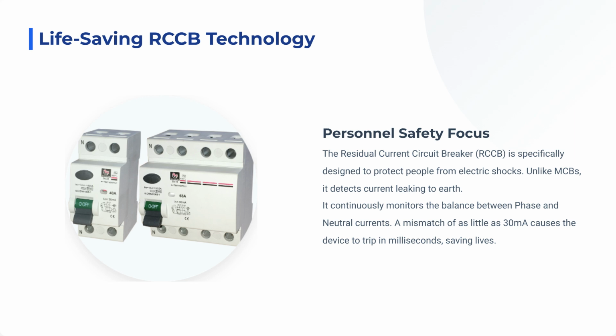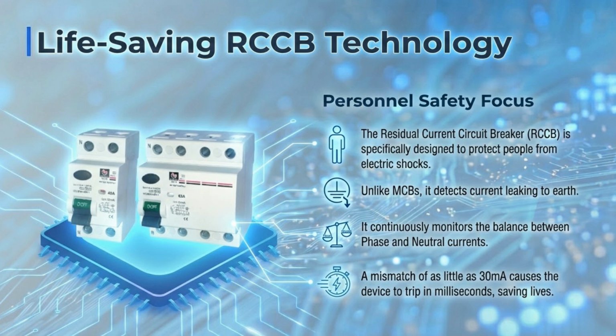The residual current circuit breaker, or RCCB, is focused on personnel safety. It detects current leaking to earth, which is a life-saving feature against electric shock. RCCBs continuously monitor the balance between phase and neutral currents. A small mismatch, such as 30 milliamperes, causes the device to trip in milliseconds.